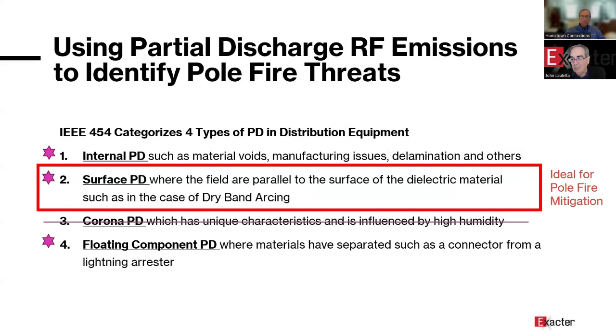And then the final one is floating components, where something has become disconnected. We found one lightning arrestor where the top wire had broken free and was just laying on top of the lightning arrestor. And that was wiping out all the communications in a broadband over power line system in a medium-sized city in Ohio. So, things like that are really important for a number of reasons other than just the equipment itself.